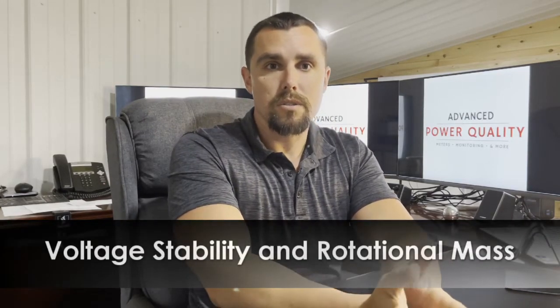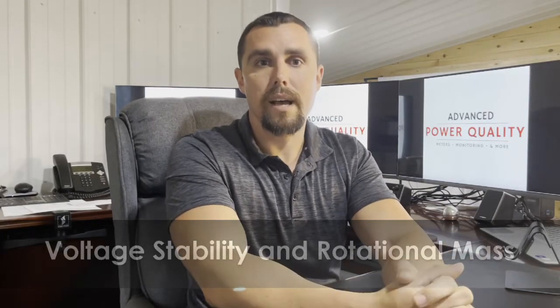What I'm getting to is your voltage stability on the distribution system is tied to rotational mass. At a power plant, the turbine is continuously moving, and that rotational mass is your voltage stability. Solar doesn't have that — you have essentially no voltage stability with solar. So say you have a power source with a customer downstream who fires up a 3,000 horsepower motor. Current goes up, voltage goes down, and the rotational mass at the power plant is what stabilizes that voltage. If you induce solar there instead, it could run into a lot of issues.